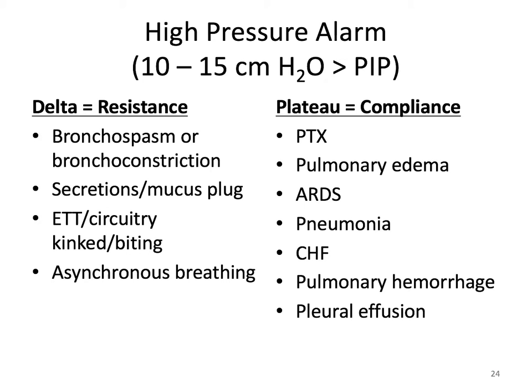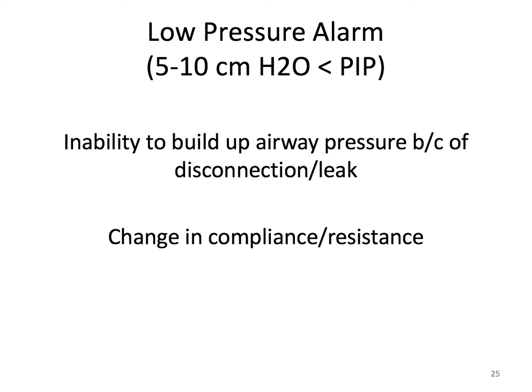Issues with delta pressure include bronchospasm or bronchoconstriction, secretions or mucus plugging, endotracheal tube or circuitry kinking or biting, or asynchronous breathing. Issues with plateau pressure include pneumothorax, pulmonary edema, acute respiratory distress syndrome, pneumonia, CHF, pulmonary hemorrhage, and pleural effusion. With a low pressure alarm — usually 5 to 10 centimeters of water below the set PIP — there's usually an inability to build up airway pressure because of a disconnection or a leak, or it could indicate a change in compliance or resistance.